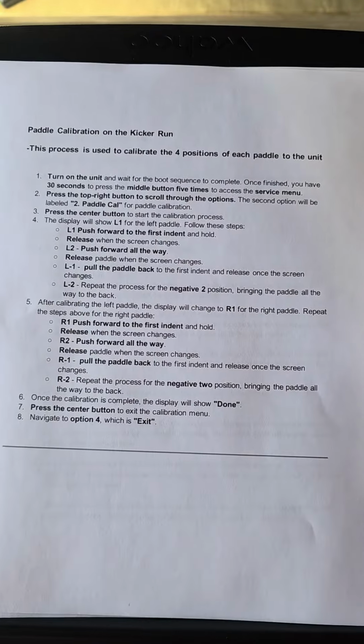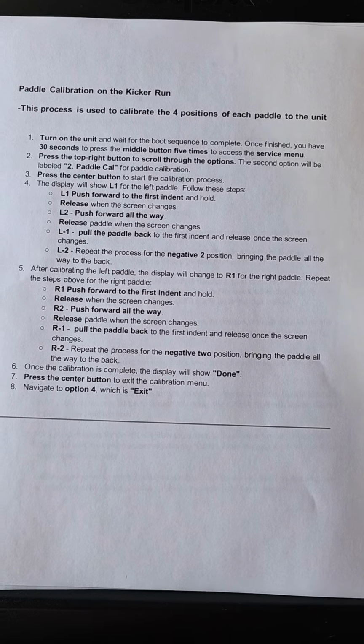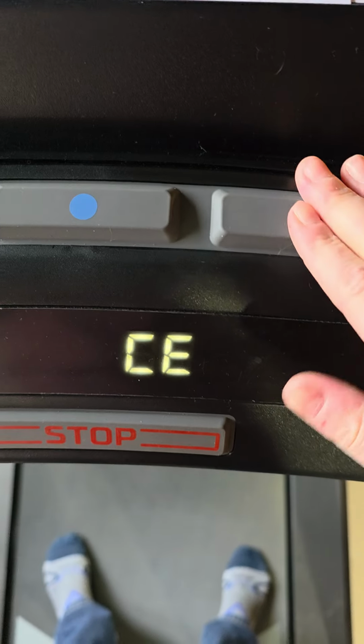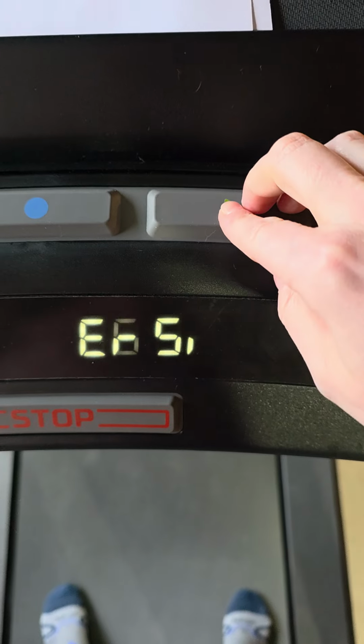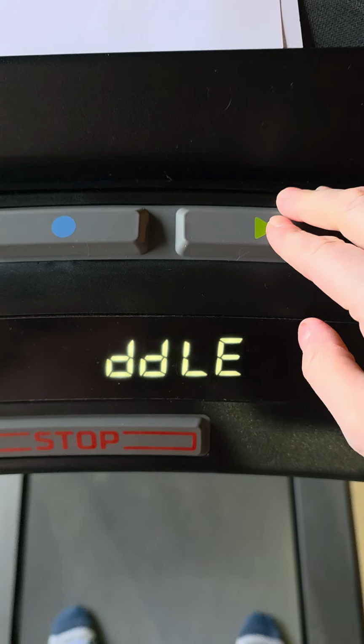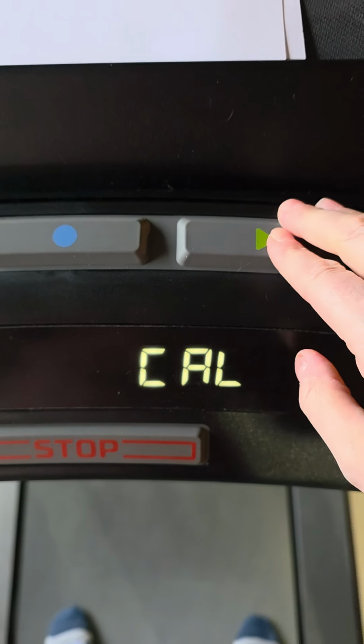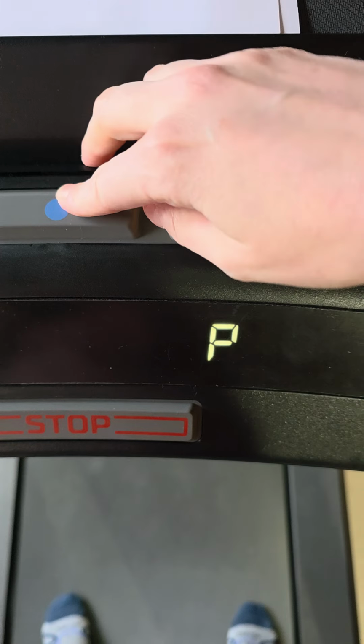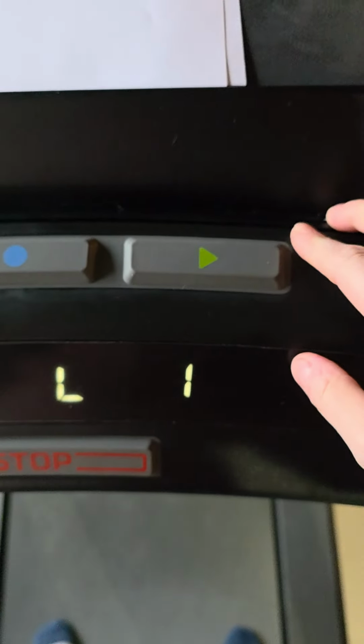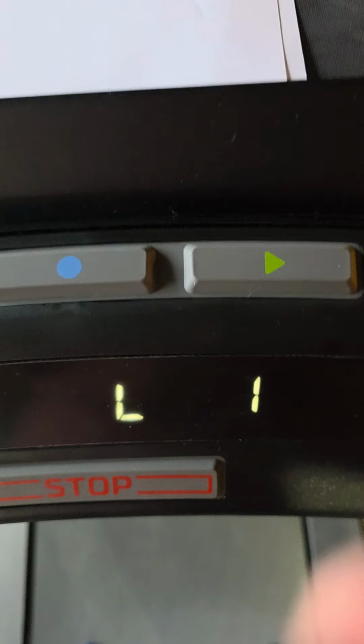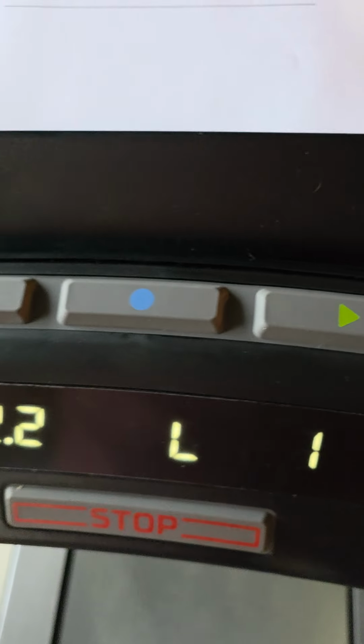So from service menu, I'm looking at the instructions provided. Turn on the unit, press the top right button, and scroll through the options. So we're going to scroll to 1, 2, paddle calibration. Press the center button to start the calibration process. And this says L1, push forward to the first indent.